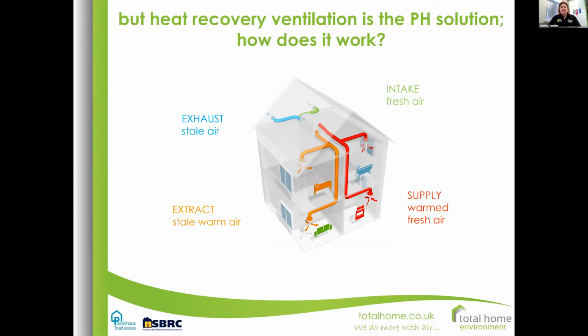So this is where heat recovery ventilation comes in. So I will try and briefly go through this. I hope nobody is already too compos mentis with regards to this, but basically here we're showing the unit in the loft area, and the ventilation unit has got 2 fans in it. One fan draws fresh air from outside, whilst the other fan gets stale air from kitchens and bathrooms. The 2 airflows cross each other, but they don't mix. The stale air gets chucked out, minus its heat. The fresh air that's now been nicely warmed then gets put via ducting and ceiling terminals through to the habitable rooms of your house, like bedrooms, living rooms, dining rooms, that sort of thing.